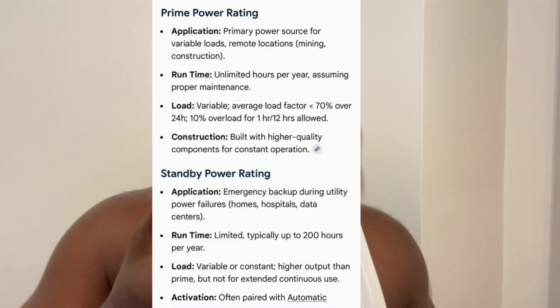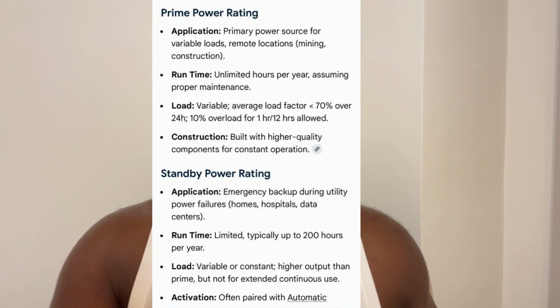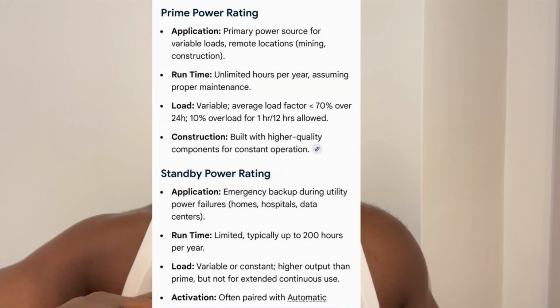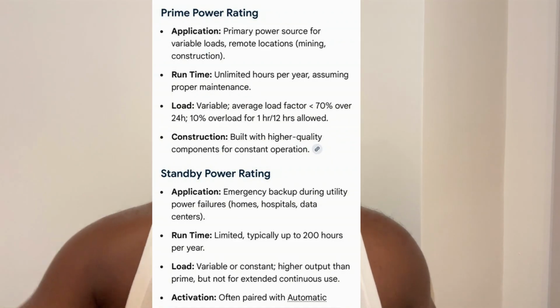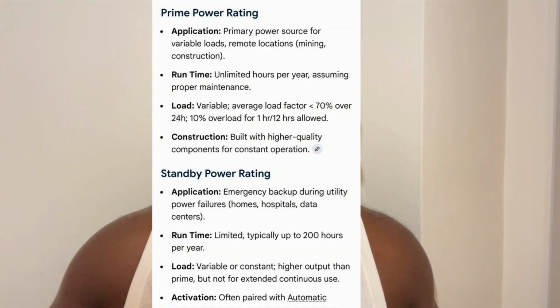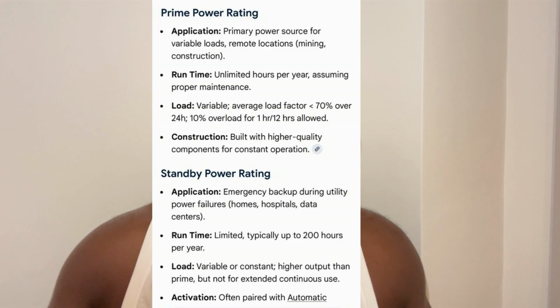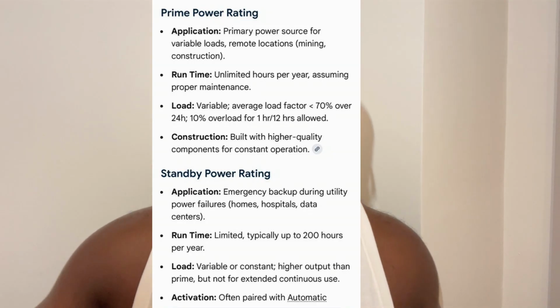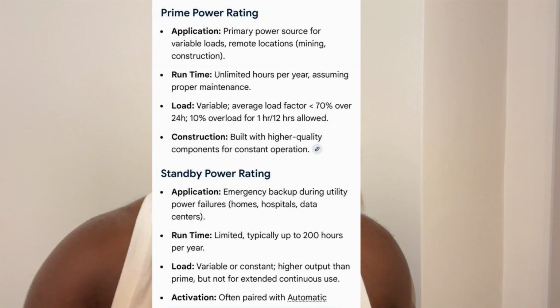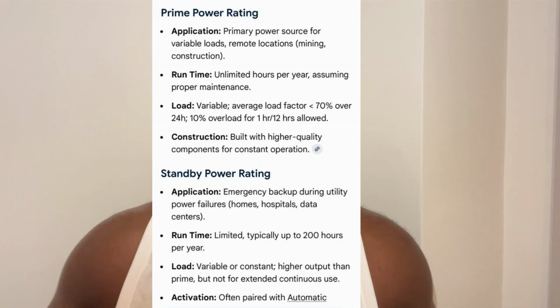And the quality of the components, the durability of the components will reflect that. But that 60 kVA can be 66 kVA. It can give you a 10% overload if you put on all your air conditioning or whatever. It gives you a 10% overload for every 1 hour in 12. That is the prime rating, and then you've got the standby rating. So these are some of the differences to consider when you're buying a generator.